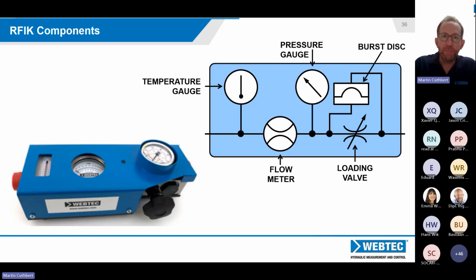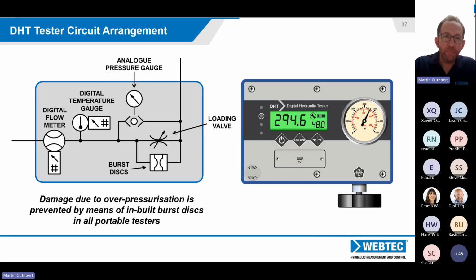If we were to look at the DHT, so this is using the turbine flow meter based system rather than your mechanical tester. Very similar, if you like. So we're going through the flow meter. We've got a temperature gauge on the side. We've got a little shuttle valve there, so we always see the high pressure side, because it's bidirectional, the flow could be coming in either direction. And then again, we've got two burst discs there to bypass the load valve should it be over pressurized.